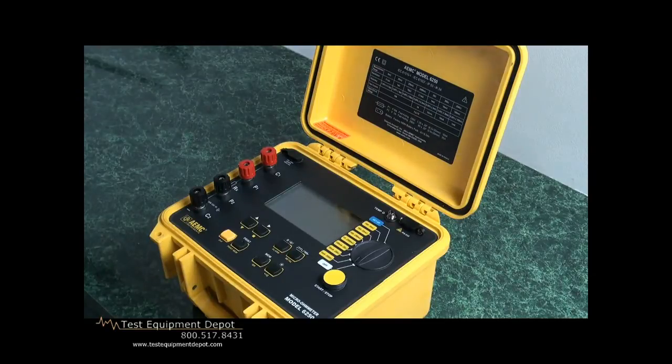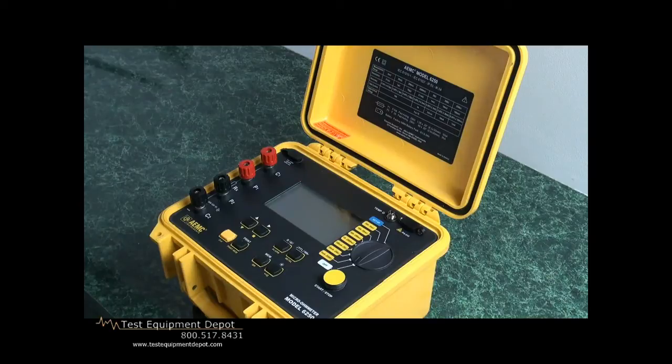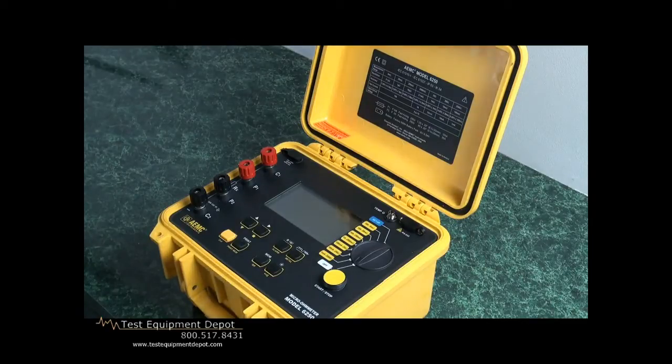I have selectable inductive or pure resistance test, because we know that when we do an inductive test, we have to keep the test signal present for a protracted period of time before the inductive reactance settles down and we get a true reading. If I do know it's a pure resistance, then I can just activate the test. It will automatically activate the test and shut itself off and wait for the next test.